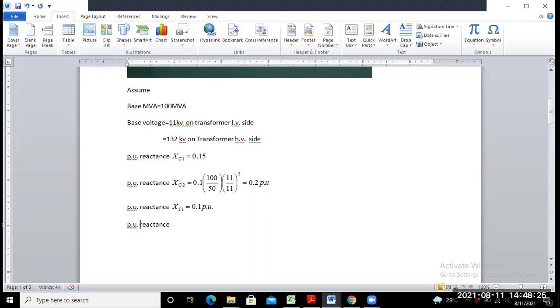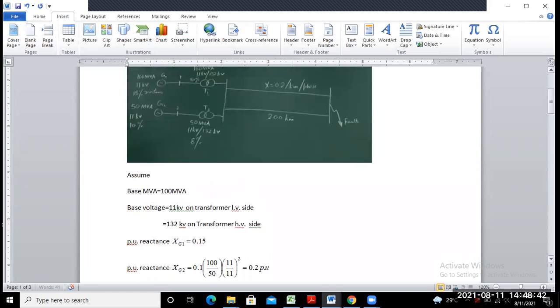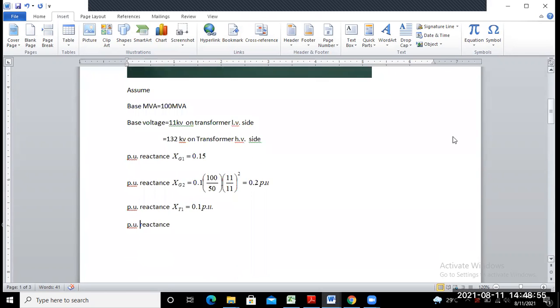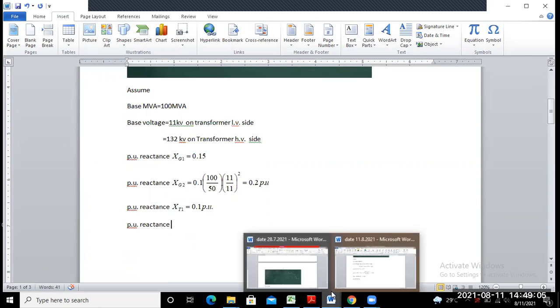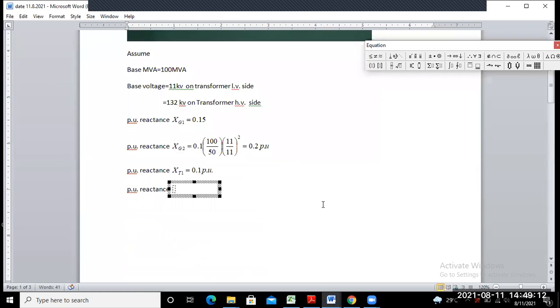Just put on the formula, whatever you know that for the new base MVA and existing their own MVA and base value. So X T2 equal to how much? On their base on MVA and KVA rating is how much? 8%. That means 0.08. So per unit reactance old value is your 0.08. And what is the MVA new and MVA old here? Put on formula. MVA new and MVA old. What is the rating here? Just put on the formula and tell me the value.